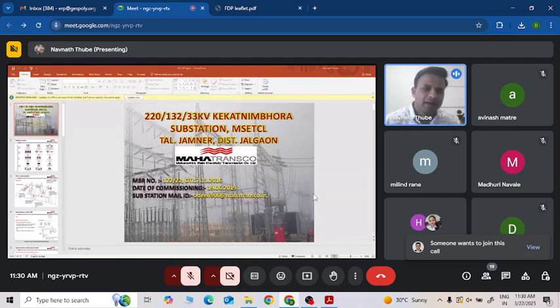This is the block diagram. The utility center means the control room. There are our EHV equipment, the power transformer, and through a single cable, this is all conventional instrument. From the conventional instrument to this MB, we only use copper cable. After that, we generate the digital bus, the fiber optic bus, and from that fiber optic bus we get all the data to our control room.